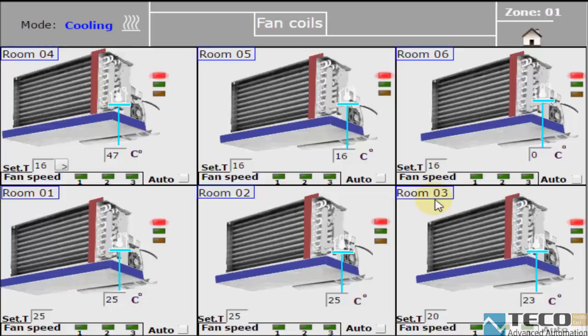We have two modes. One is manual, where the fan speed is chosen by the user. Or we have the auto mode, where the system will choose the fan speed. This is done based on the difference between the set point and the room temperature.